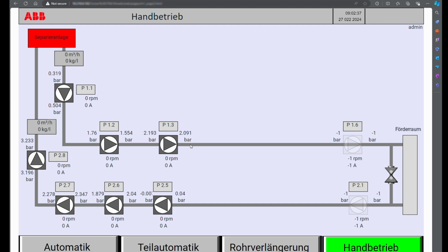But what we can notice here, which is also interesting, is a difference: the outlet pump pressure is 1.5 bars, but after 1.5 kilometers, the pressure has risen by 0.6 bars. This is only because the height is different - pump 1.3 is much lower than pump 1.2, so that's the only reason the pressure is higher on this side. Then the outlet pressure is pretty much the same as the inlet pressure.